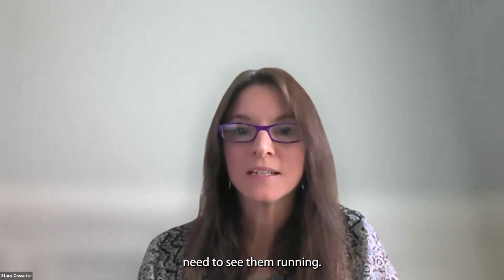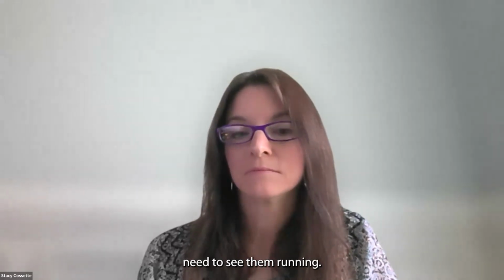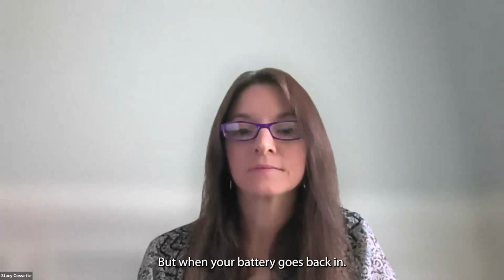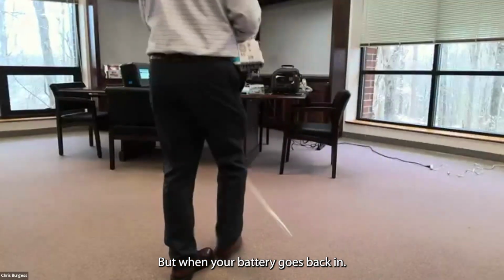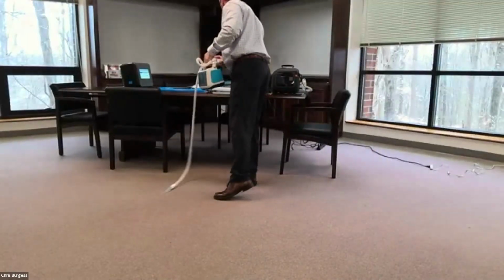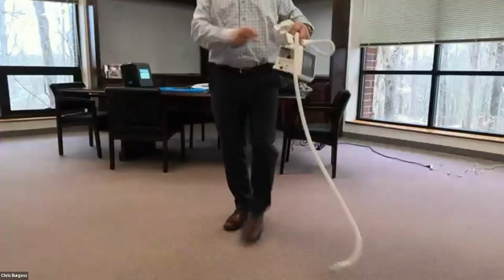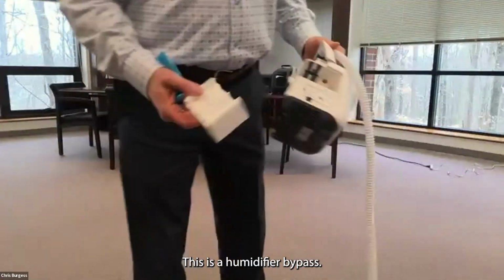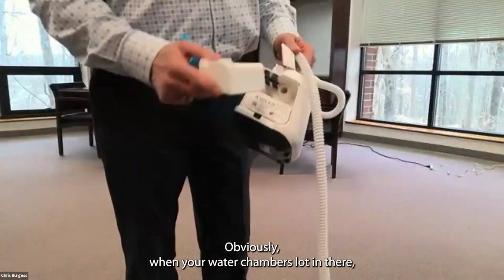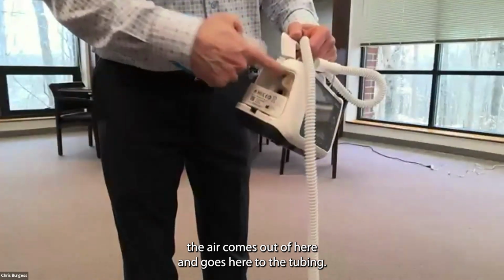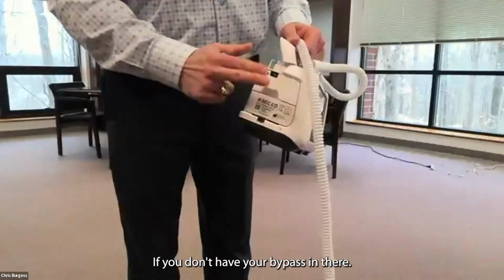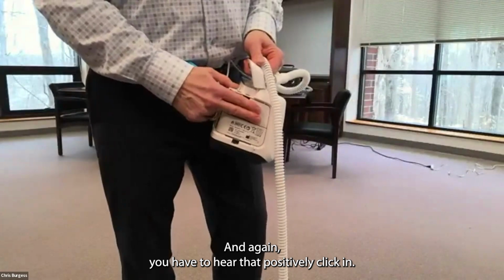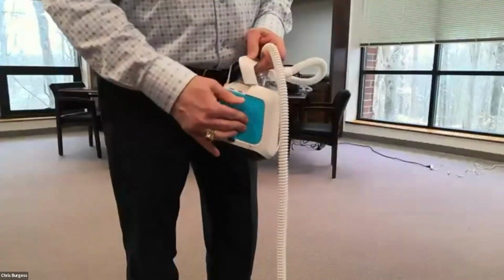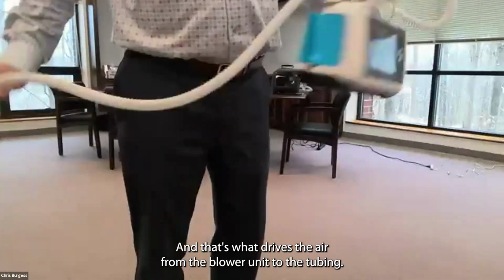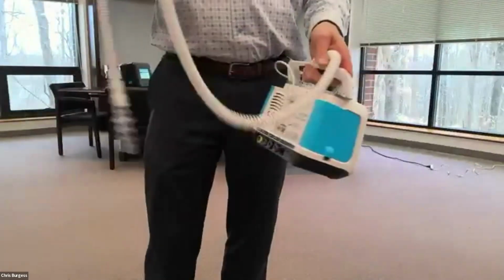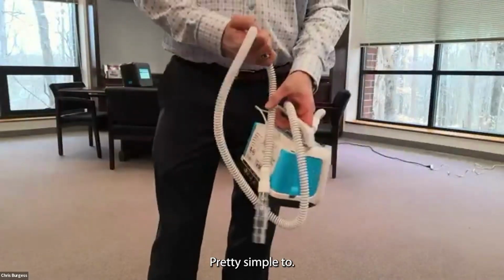I don't know that we really need to see them running. So then your battery goes back in. This is a humidifier bypass. Obviously, when your water chamber's not in there, the air comes out of here and goes here to the tubing. If you don't have your bypass in there, and again, you have to hear that positively click in, that's what drives the air from the blower unit to the tubing. Pretty simple now.